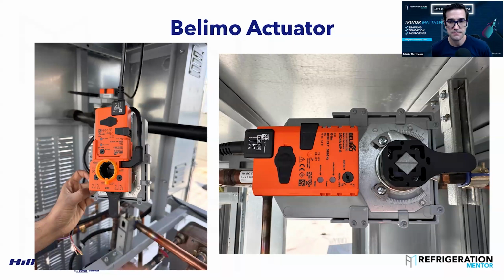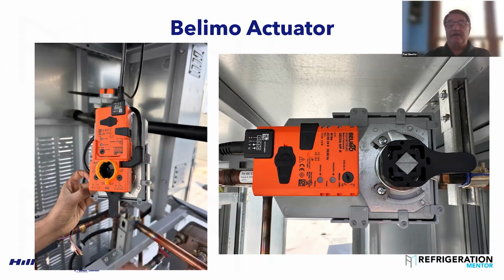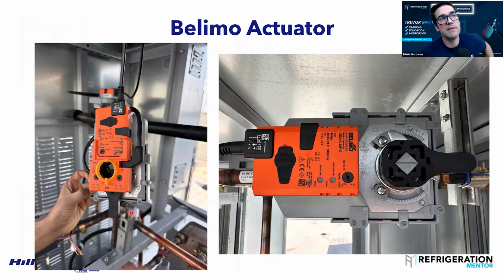Yep. All right, so one of the other things we do at startup, if we have heat reclaim or hot water reclaim, you want to check your valve to make sure you're circuited so that during the off position, it goes from compressor to condenser, not through your reclaim. So you want to make sure these valves are oriented correctly. You stroke them, give them a 0 to 10, and watch them go fully open. Take them back to 50%, watch them stop, and then go back to 0. You want to make sure this stuff works. This is what we call getting ready to start the rack. We're making sure that when you roll the windows up, they go up. When you roll the window down, it goes down. And when you push the window for the left, the right one doesn't go up and down. To put it in layman's terms. And so this is something that you may not have seen on a rack before.